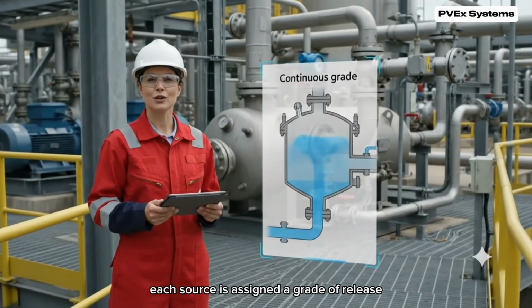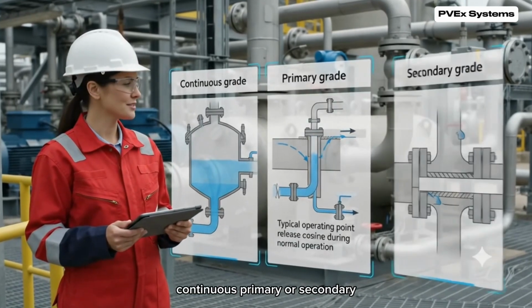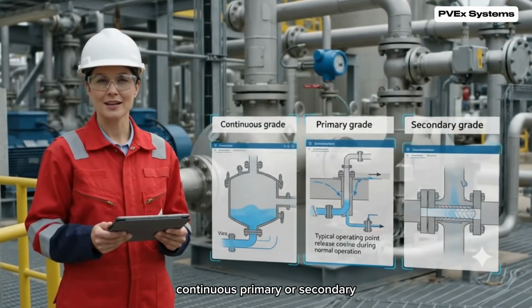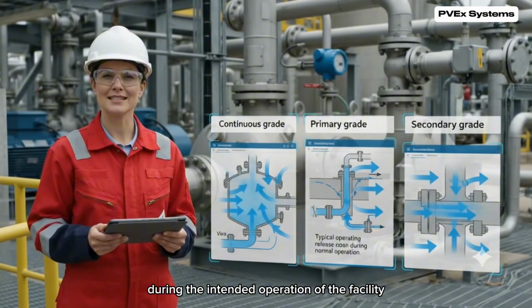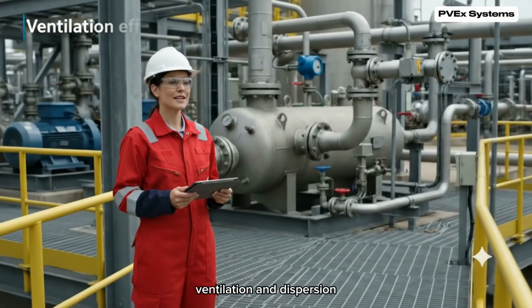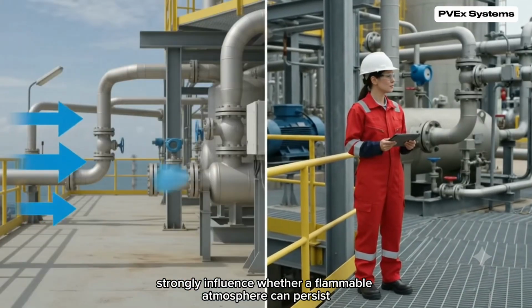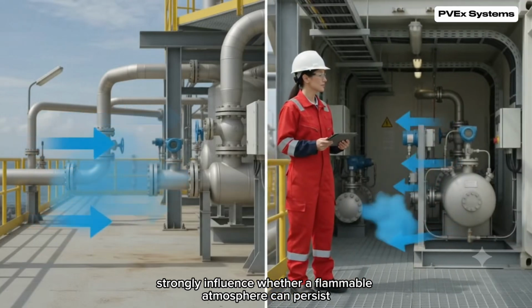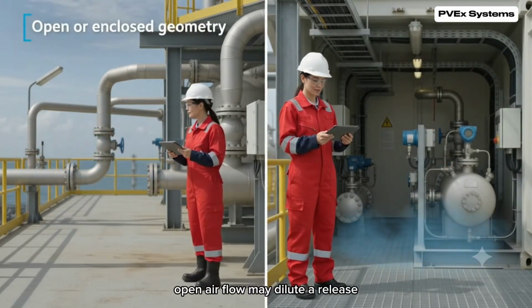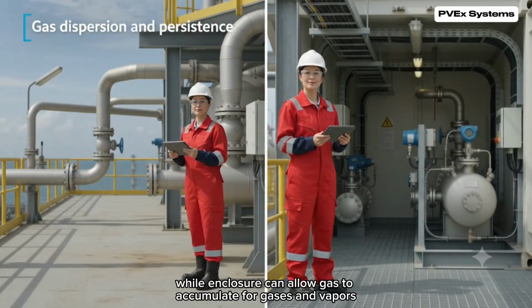Each source is assigned a grade of release: continuous, primary, or secondary, based on how the release may occur during the intended operation of the facility. Ventilation and dispersion strongly influence whether a flammable atmosphere can persist. Open airflow may dilute a release, while enclosure can allow gas to accumulate.